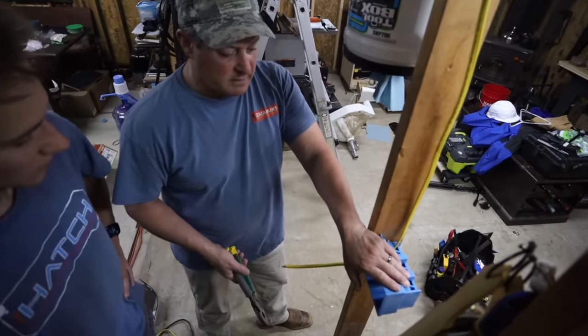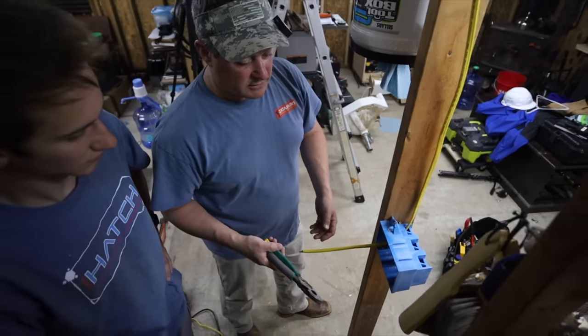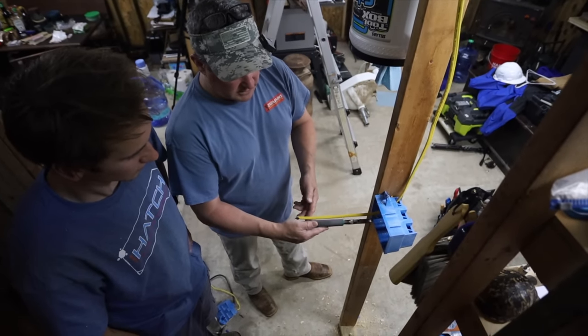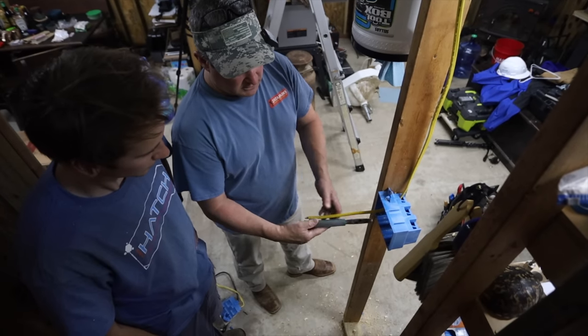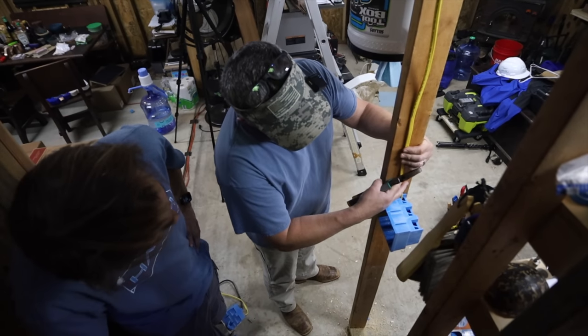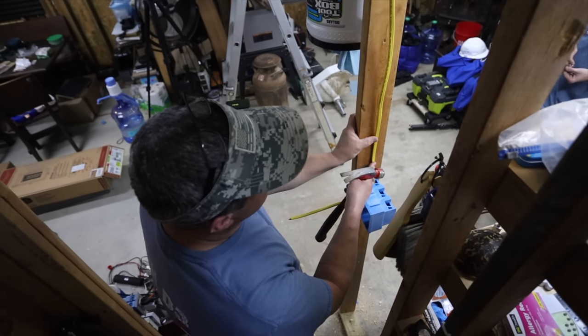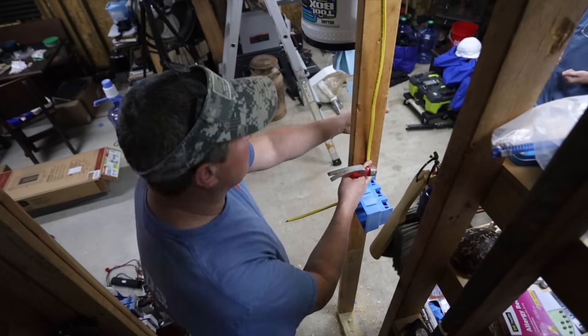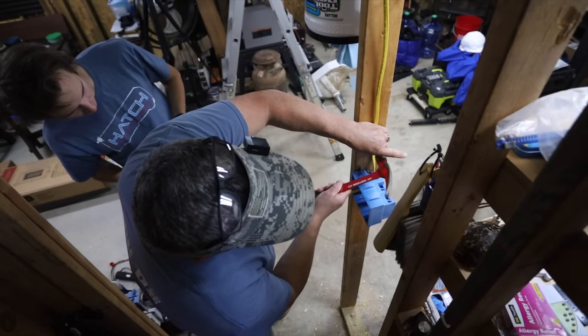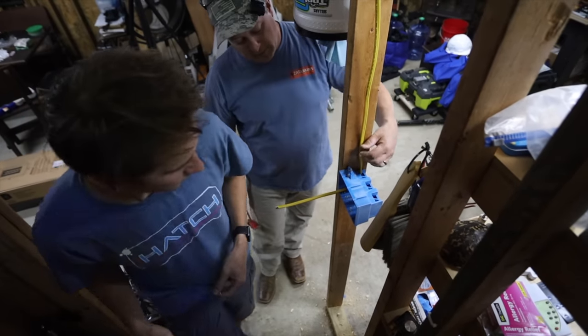You want to make sure you've got enough to work with past the box. I like to use your dykes as a measurement — should give you plenty. You've got to have a staple close to the box within about four inches or less. We might have to use some spreaders to keep that wire in the center of the stud. But for right now, just to hold, let's get a staple in temporarily, and then we'll come back and attach whatever we need to shortly. Let's get a wire count, see how many we've got here before we permanently start stapling.